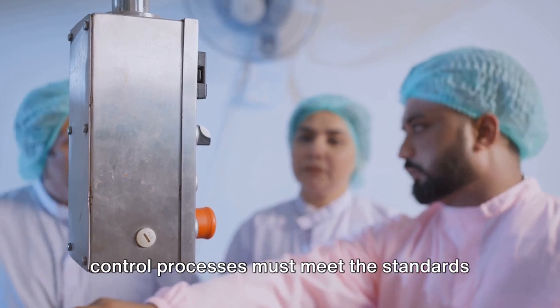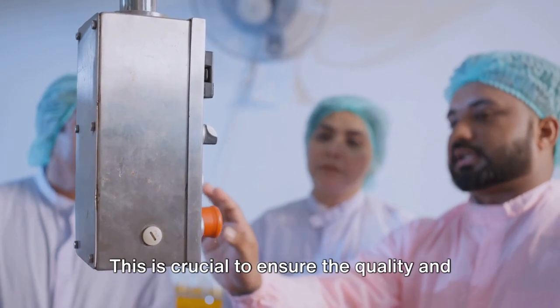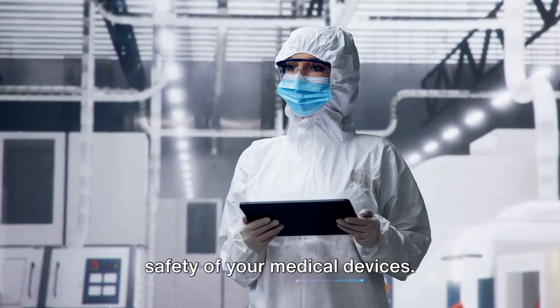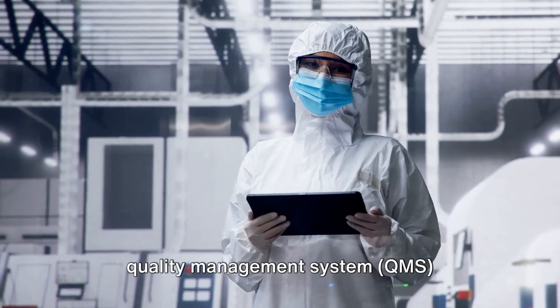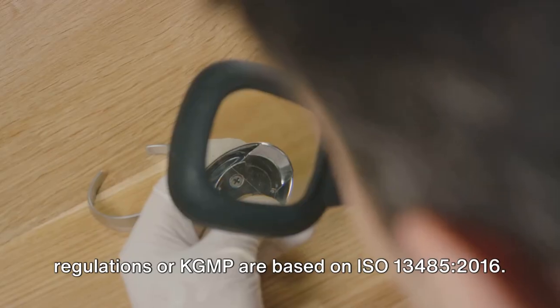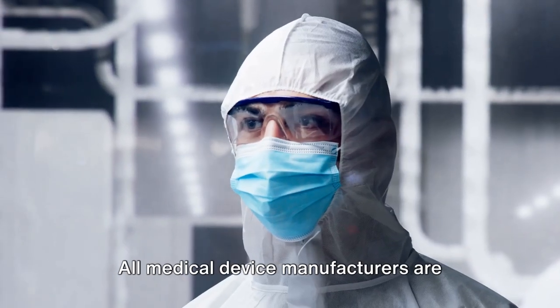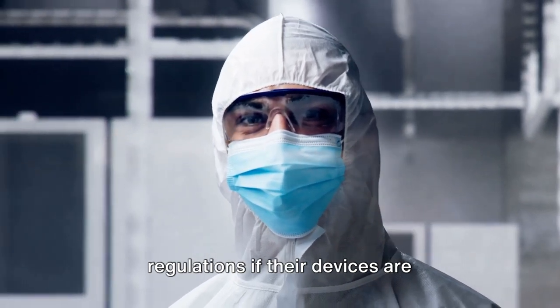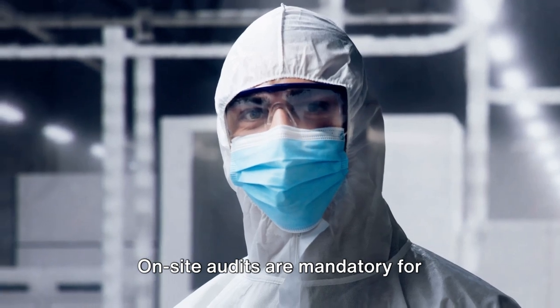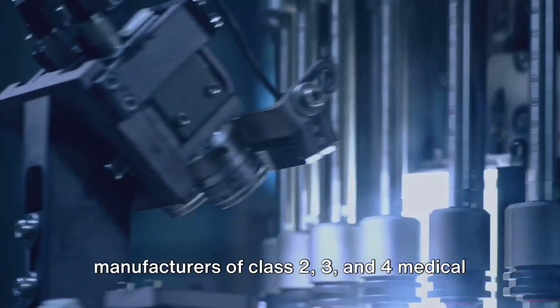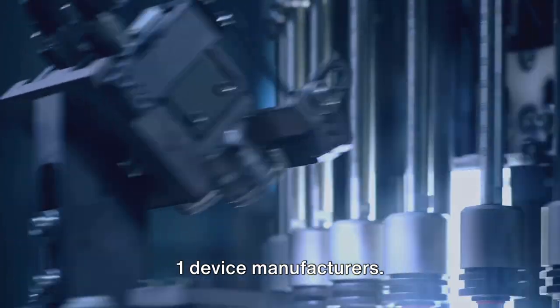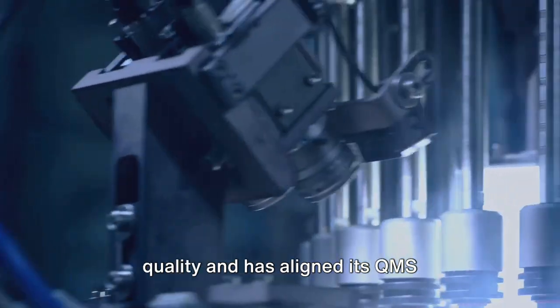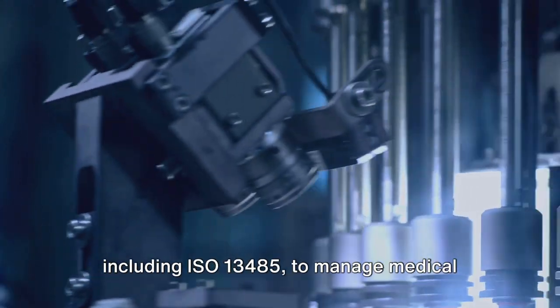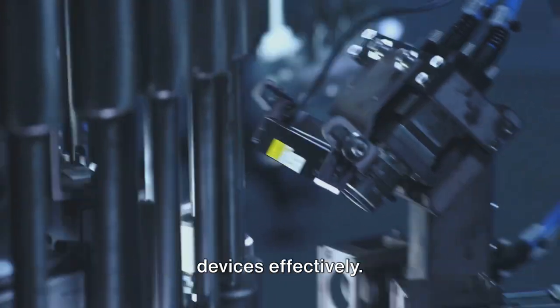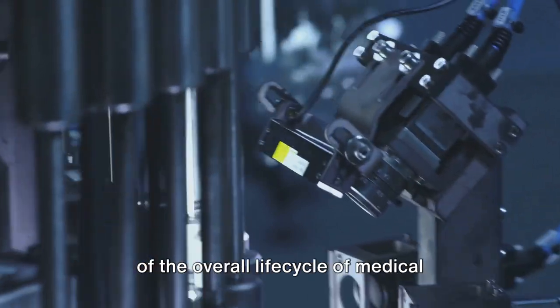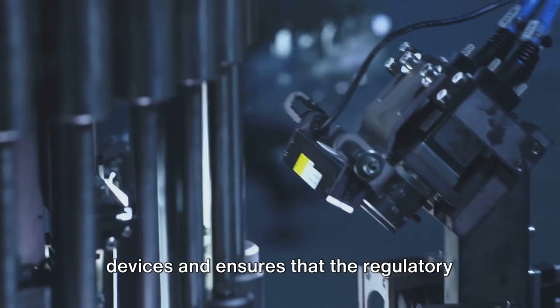Finally, your manufacturing and quality control processes must meet the standards set by the MFDS. This is crucial to ensure the quality and safety of your medical devices. In South Korea, the Medical Device Quality Management System, or KGMP, is based on ISO 13485, 2016. All medical device manufacturers are required to comply with these QMS regulations if their devices are distributed within the country. On-site audits are mandatory for manufacturers of Class 2, 3, and 4 medical devices, while they are elective for Class 1 device manufacturers. The MFDS emphasizes the importance of quality and has aligned its QMS regulations with international standards, including ISO 13485, to manage medical devices effectively. This alignment facilitates the management of the overall life cycle of medical devices and ensures that the regulatory system is harmonized with global regulations.